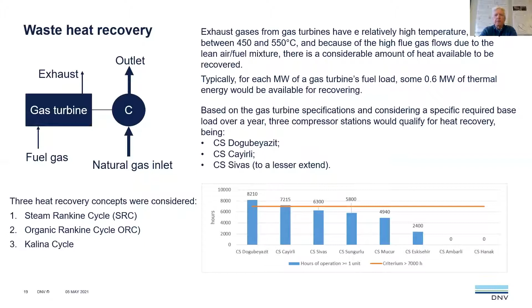Based on the typical loads and capacity involved, a cash flow analysis of the application of an organic Rankine cycle heat recovery system has been done. The organic Rankine cycle is considered to be the most appropriate technique to be applied at gas compressor stations. The cash flow analysis, however, showed that application of an ORC is not economically viable. Based on an investment of some 6.3 million euro, a project payback time of 16 years has been calculated. Considering the anticipated life of the ORC system, the investment will not pay out.